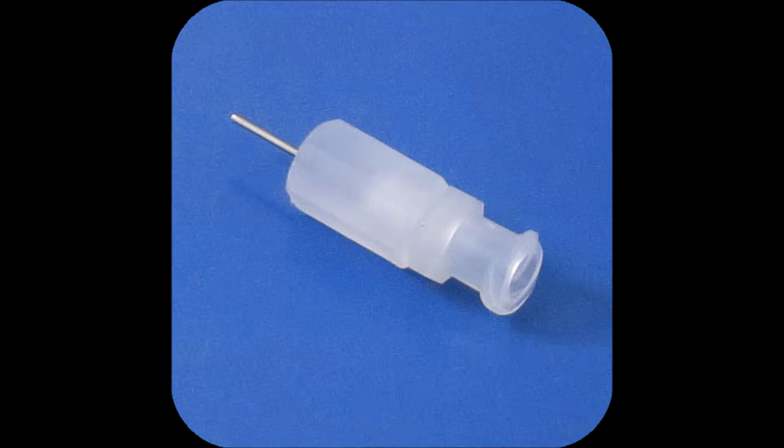These fittings consist of three components: the stainless steel element, the body, and the connection type — either barbed, luer, or thread. They accommodate the range of micro-bore tubing from 10 thousandths to 50 thousandths of an inch inside diameter.